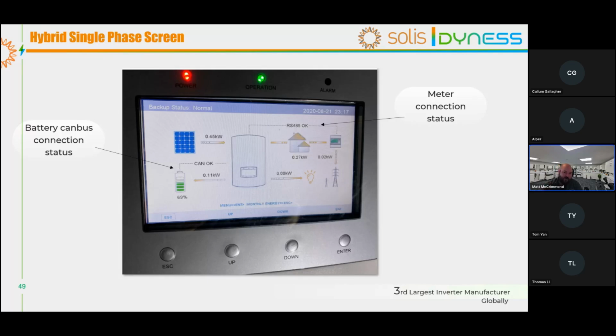You can also see on this where it says 0.02 kilowatts, if you were looking at the customer smart meter and it was showing you a value of maybe 1 kilowatt, 2 kilowatts, but you were seeing zero there, but it said RS485 OK, then we would always indicate that that's an issue with the CT. On the meter itself, you can actually scroll through the menus, and you can see what the live current is, what the live voltage is, and it'll read that information. It will show you voltage because it's powered, because that's where the voltage reference is, but the CT is reading the current of the cable. If that's at zero, then you would check the CT to make sure, as I said earlier on, that it's clipped round properly, or that it's not damaged.